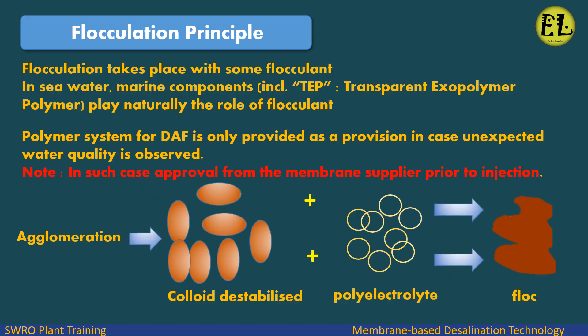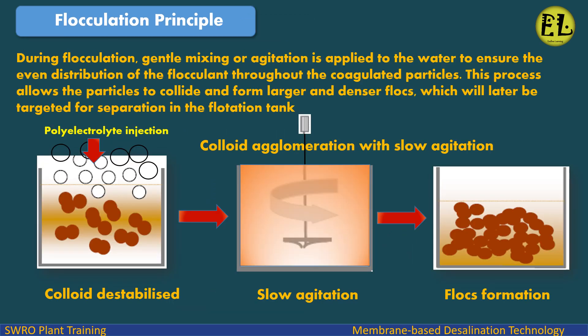Flocculation principle: Flocculation takes place with some flocculant in seawater. Marine components, including TEP (Transparent Exopolymer Particles), naturally play the role of flocculant. A polymer system for DAF is only provided as a provision in case unexpected water quality is observed. Note: in such a case, approval from the membrane supplier is required prior to injection. During flocculation, gentle mixing or agitation is applied to ensure even distribution of the flocculant throughout the coagulated particles, allowing particles to collide and form larger, denser flocs which will later be targeted for separation in the flotation tank.